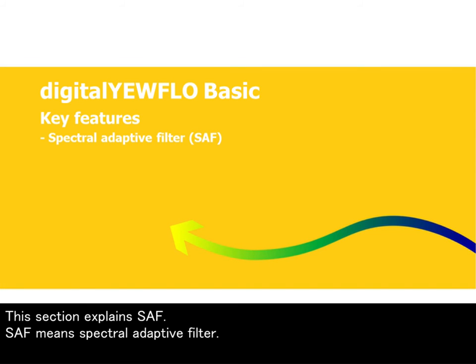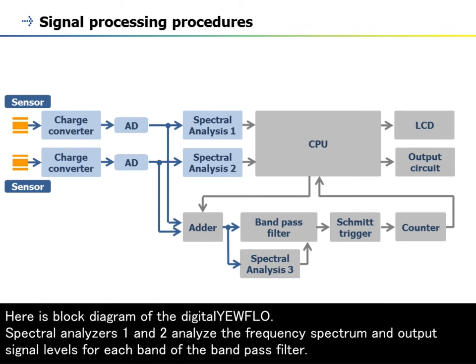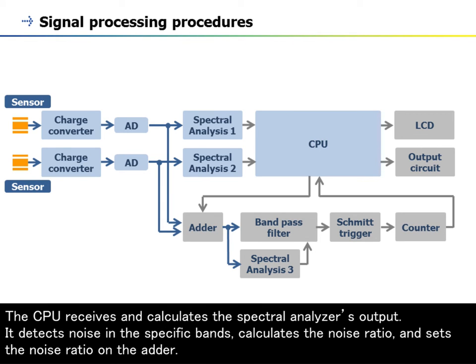This section explains SAF. SAF means spectral adaptive filter. It is a technology for noise detection and calculation of the signal-to-noise ratio. Here is a block diagram of the digitalYEWFLO. Spectral analyzers 1 and 2 analyze the frequency spectrum and output signal levels for each band of the bandpass filter. The CPU receives and calculates the spectral analyzer's output. It detects noise in specific bands, calculates the noise ratio, and sets the noise ratio on the adder.